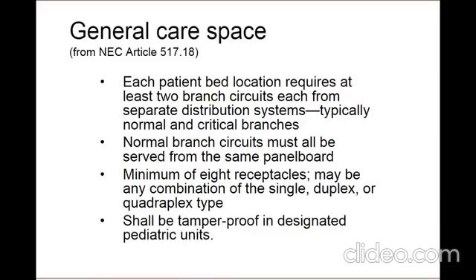Now we'll take a look at some of the special requirements in the general and critical care spaces. In a general care space, each patient bed location requires at least 2 branch circuits, one from the normal system and one from the critical branch. The normal branch circuit may alternatively be a critical branch circuit if that circuit is supplied from a separate transfer switch from the one supplying the other critical branch circuit. When more than one normal branch circuit is supplying an individual patient bed location, all normal circuits must originate from the same panel board. A minimum of 8 receptacles must be provided at the patient bed location. These 8 receptacles may be any combination of single, duplex, or quadruplex type.